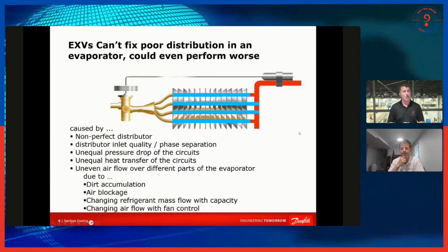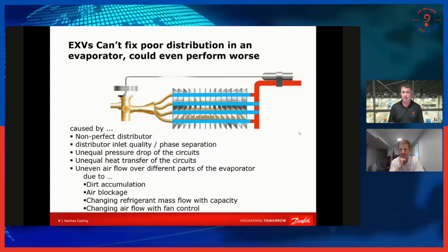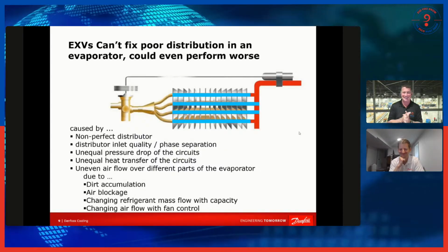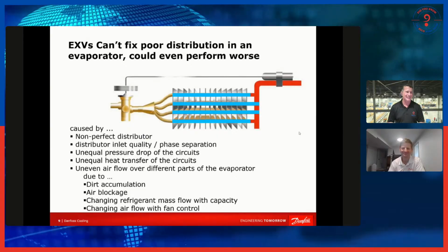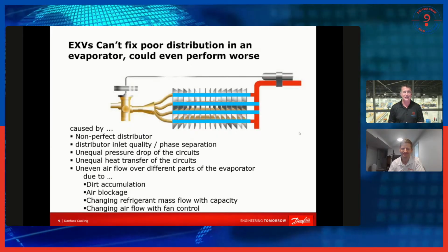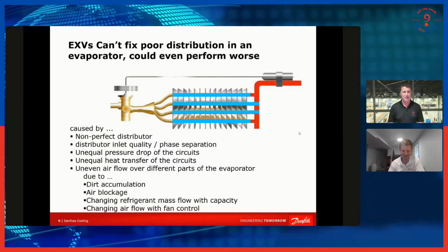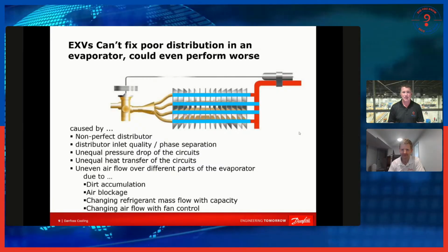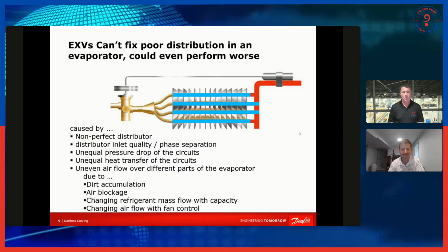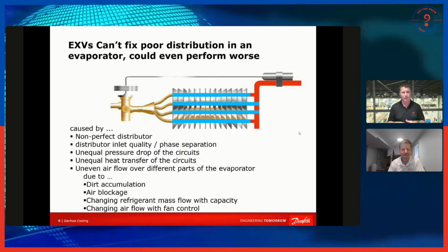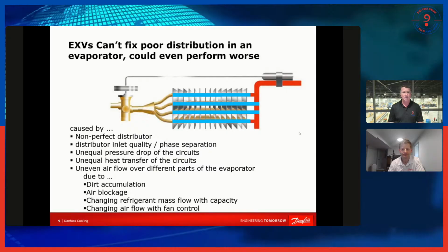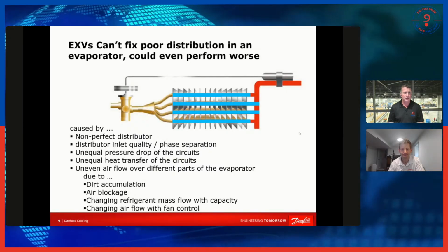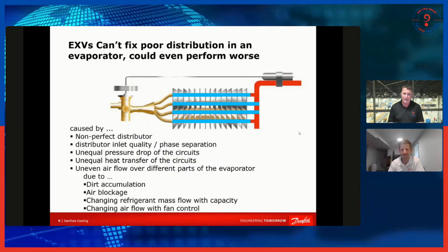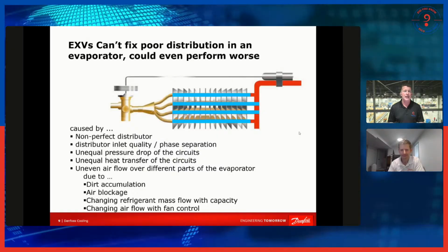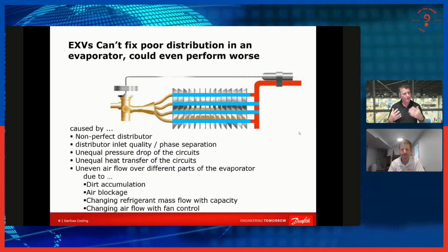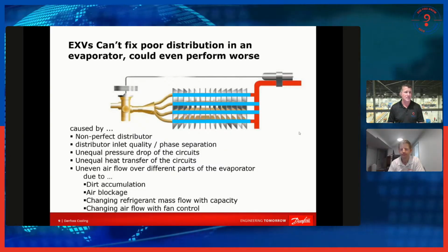Not saying that there are improperly commissioned systems in our industry without saying that we have a lot of improperly commissioned systems in our industry. One of the things that we used to think of a lot of times when we're looking at adjusting our airflow on an air conditioning system, many times if we're wanting to readjust our sensible heat ratio, we would reduce airflow a little bit, and the thermostatic expansion valve could try to compensate in some of that.